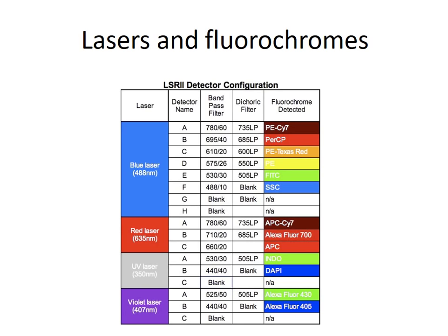And the difficulty is if you have 7 or 8 cellular markers that you need to identify, that means you need 7 or 8 different colours to enable it to identify each one of those. And if you have increased number of lasers, you have the capacity to increase the number of fluorochromes you can use. Okay?